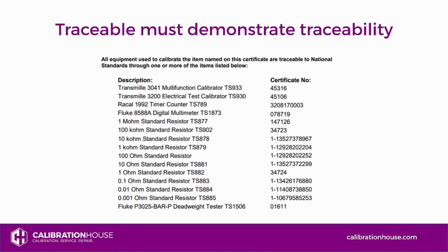So you can see here a list of equipment with the relevant certificate numbers. So this is the calibration company's equipment, showing that their test equipment has been calibrated to, in this instance, UKAS. And therefore, when they use that equipment to calibrate a customer's equipment, the calibration is traceable to UKAS through the calibration company's test equipment.